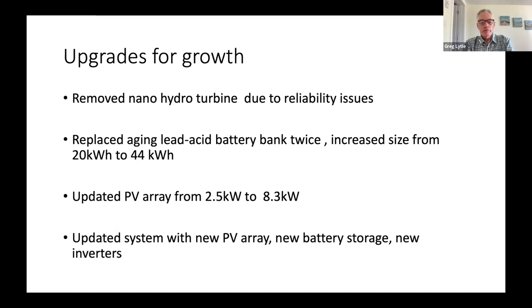Over time, I think we replaced the lead acid batteries three times, and we ended up updating from about a 20 kilowatt hour system to a 44 kilowatt hour system, and updated the PV array from the original small 2.5 kilowatts to 8.3 kilowatts about 5 years ago. And then in the last year or so, we've done a major update again, where we've added a new PV array, new battery storage, new inverters, and a new control system to integrate everything together to, again, improve the reliability and minimize our generator use.